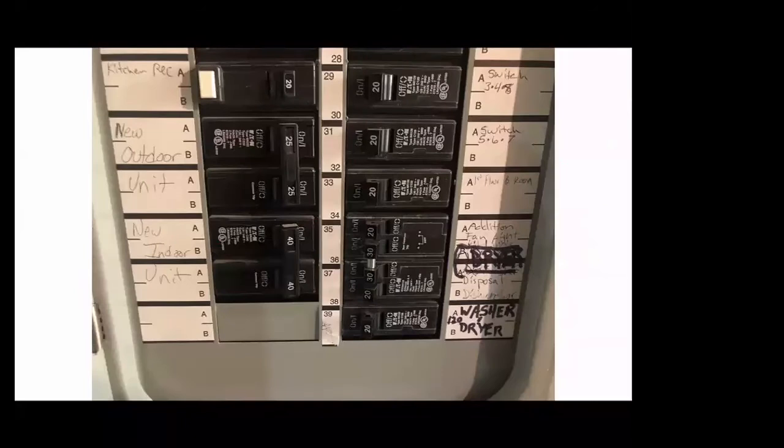And then this is the air conditioner on the inside, the blower, the air handling unit. This is the compressor condenser unit on the outside. These were for the dryer, but there's a gas dryer now, so I guess I don't need 240 for that, because it's not trying to heat it up at the same time it's trying to spin it. Now this is the sub panel, and inside the sub panel you have the indoor unit, that's the air handling unit in the attic, and there's the outdoor unit, that's the compressor condenser unit in the split system. And if you were here for the previous 40 minutes of competence, you know what I'm talking about. This is baseboard heating, so it needs a little extra oomph as well. But this is just like a bathroom, and this is for outdoor. So there's like an outdoor electrical receptacle.